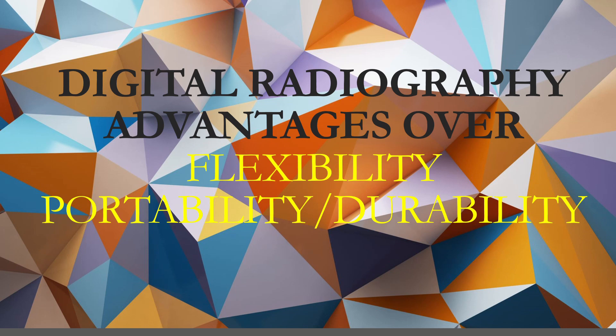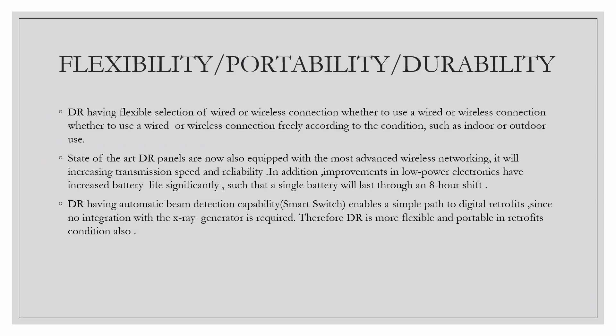Our next topic is flexibility, portability, and durability. DR has flexible selection of wired or wireless connection, usable according to the condition — such as indoor and outdoor or portable X-rays. State-of-the-art DR panels are equipped with advanced wireless networking, increasing transmission speed and reliability. Improvements in low-power electronics have significantly increased battery life, such that a single battery will last through an eight-hour shift.